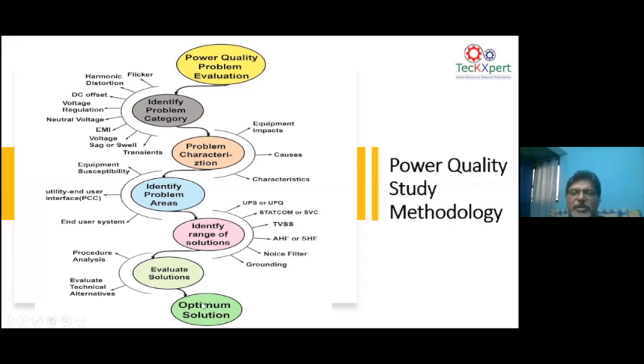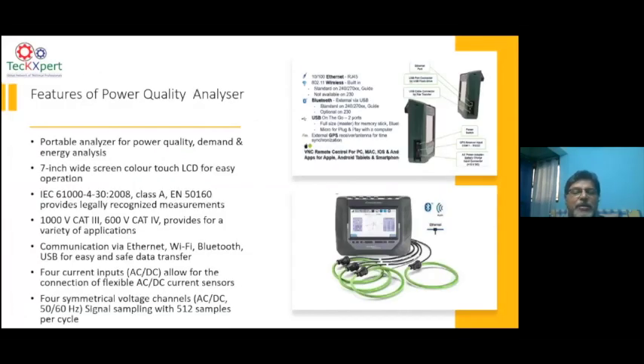This is how you should do the power quality methodology. Now we have certain analyzers we can use. The type of analyzer that you should use for power quality analysis, number one, it should comply to Class A, IEC 61000-4-30 Class A. When I say Class A, there are Class B analyzers which are not according to the required standards.